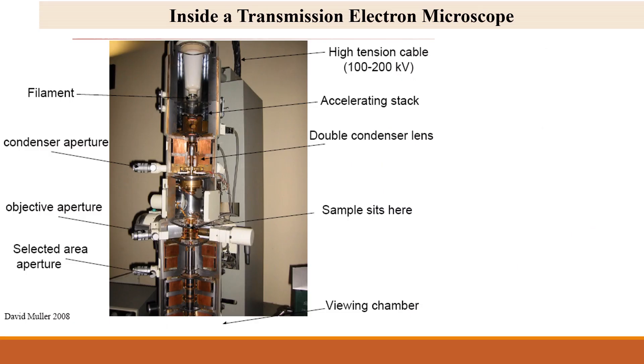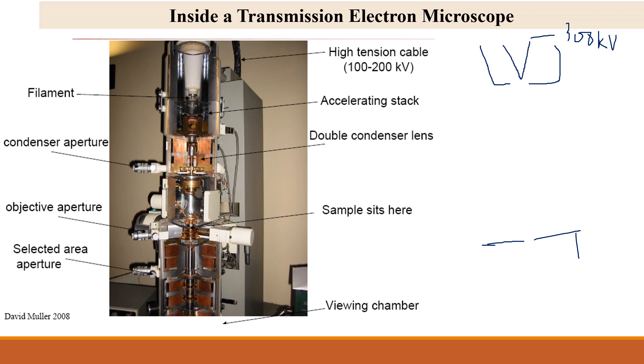Inside the transmission electron microscope, whether it is a field emission gun or thermionic emission gun, there is a sharp filament below which is a Wehnelt cap. This filament is connected to minus 300 kV in a 300 kV system, or minus 200 kV in a 200 kV system. The final stage in the acceleration stack is grounded to 0 kV.